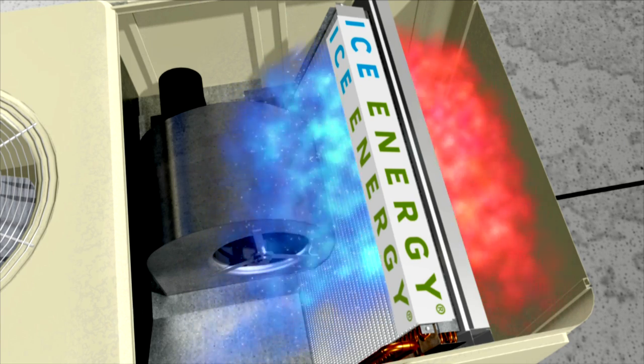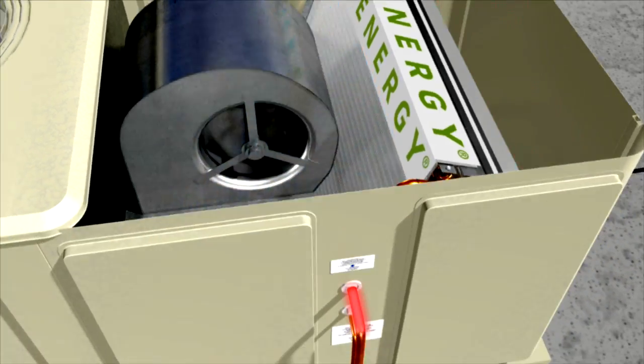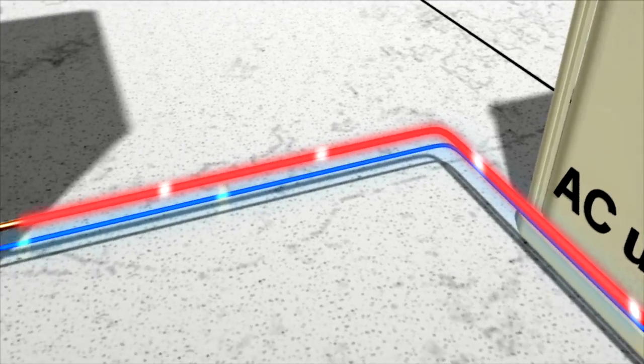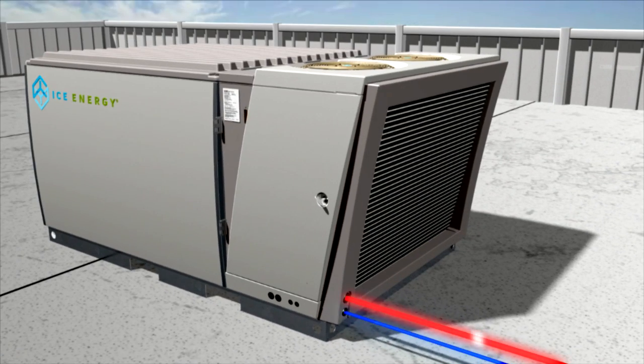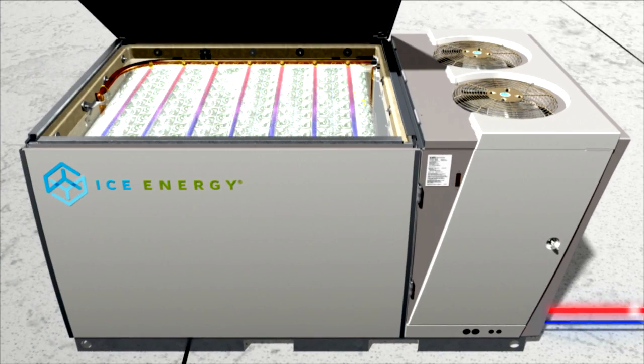The cool air continues on its path into the building, while the hot refrigerant travels back to the IceBear. Rather than using the AC unit's compressor, the IceBear then uses the cold energy stored in the ice to cool the refrigerant.